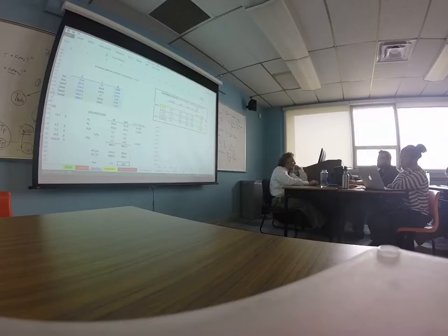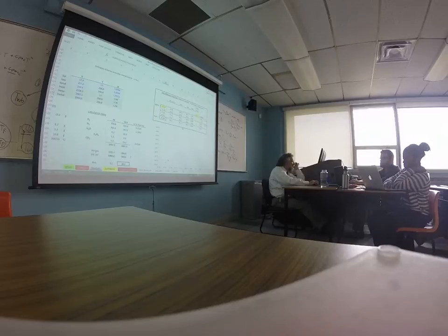And here is a plot of that. So it's just the Newton method to find the 0 of a function. It's called the Newton method. You guys have used it a million times, I'm sure. Here is just 2 iterations, and you're done because it's almost linear. So it's the case of having the enthalpy and wanting to find the more precise wet bulb temperature. So this one is not far, but you see 47.55 ends up being 47.84. So we know the wet bulb temperature now, and you could compare that with whatever you measure.